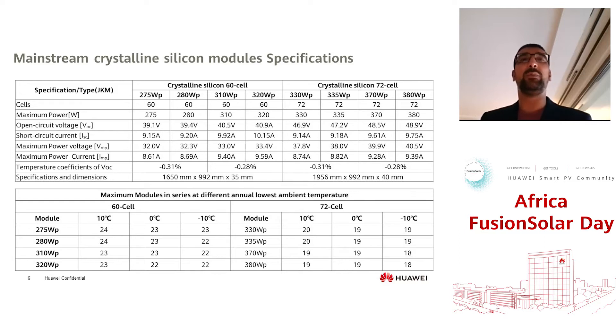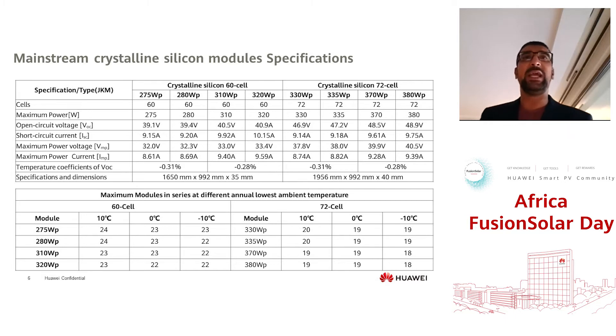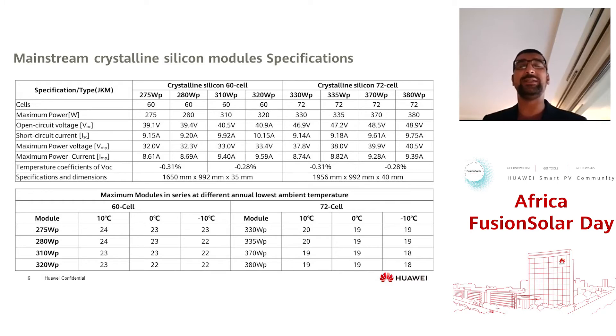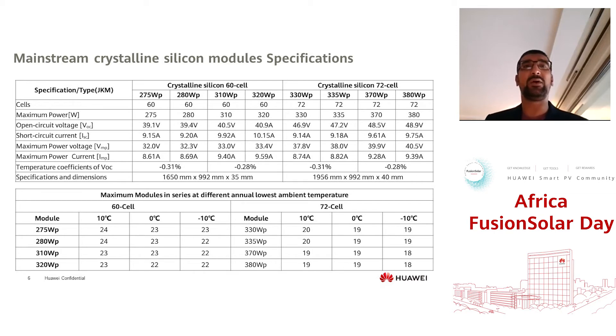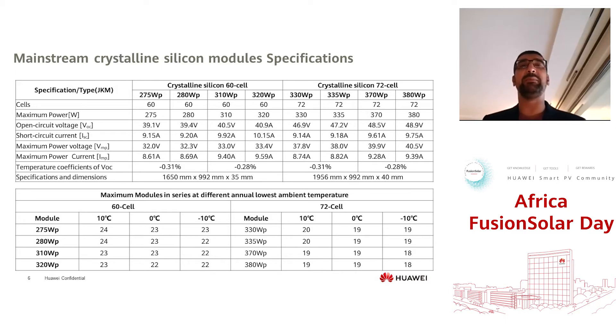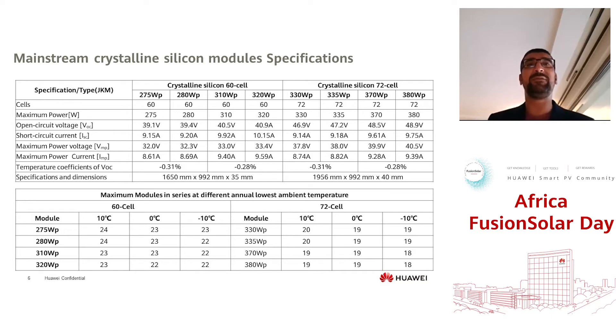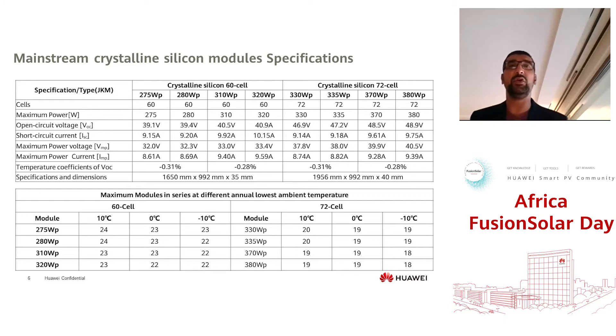For example, with a 60-cell module — a 280 watt PV module — you can see the Vmpp and also the temperature coefficient Voc value taken from the datasheet. Based on those two parameters you can calculate exactly how many modules per string. With a minimum temperature of 10°C, you can comfortably connect 24 PV modules in a string.